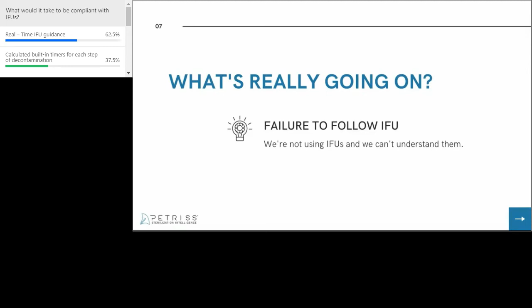Now, even though the sterilization parameters are a critical part of instructions for use, if you look closely at any IFU, there are multiple steps, multiple instructions through the entire workflow. There are instructions based on particular manufacturer recommendations for cleaning, for disassembly, for inspection, for packaging, all of these things that happen prior to those sterilization parameters. And oftentimes, there are even recommendations and instructions for storage after sterilization. All of these IFUs have to be followed to be compliant.